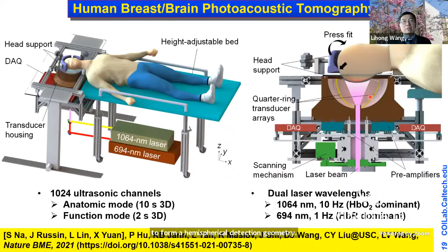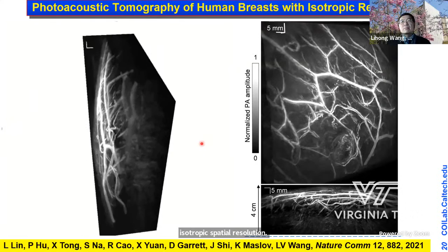The rest of the system is quite similar to the previous breast system. The exception is that we have a bowl-shaped structure instead of a ring-shaped structure, and we have 1024 elements instead of 512 elements. We rotate the arcs. There are 4 arcs distributing the 1024 ultrasound transducers, and we rotate them to form a hemispherical detection geometry. Then we run 3D image reconstruction to form an image. This is an example breast image. Again, the key advancement is that now we can provide isotropic spatial resolution, so you can see blood vessels in detail in all 3 dimensions.